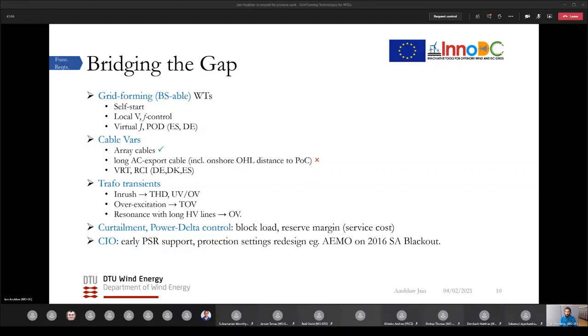So, to see measures that can allow stable, controlled islanded operation from wind turbines. And I think Siemens Gamesa and Scottish Power Renewables, who have recently demonstrated complete grid forming operation on an onshore wind farm without any external grid, have also come to similar conclusions: that protection settings need to be looked into or changed, especially in areas where there is high wind power penetration. And I think they even talk about having some passive load just for the sake of allowing this operation, so burning of energy.